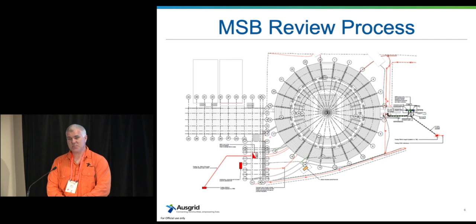If they are longer, and it happens very easily, especially with the way they are currently drawn up at the moment, which within Ausgrid is under review, hopefully to come out soon, they are very short. Because at the moment, if it's a substation supply, it's immediately adjacent wherever practicable. So that means the next room, not 50 metres down the opposite end of the building. So at those times, if we are not aware because we were never given this diagram here, it could be a very easy one that we've just paused the installation energisation, and I know how much stress and anxiety that can cause for the job site because we have milestone payments and all the rest of it. So the guys in orange, we are well aware of what those ramifications are, but again, we've got that legislative burden on us to make sure that it is compliant to the standards and our requirements as well.